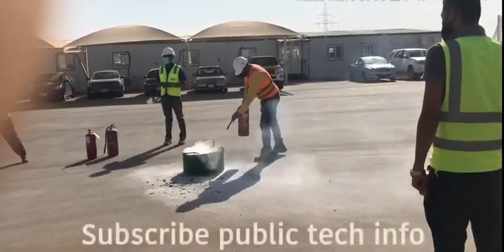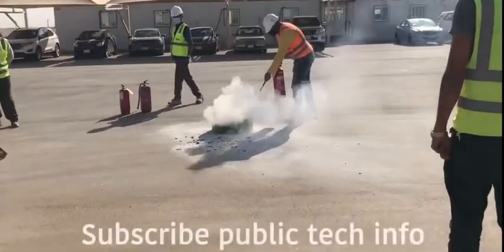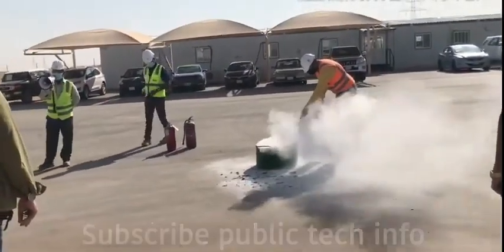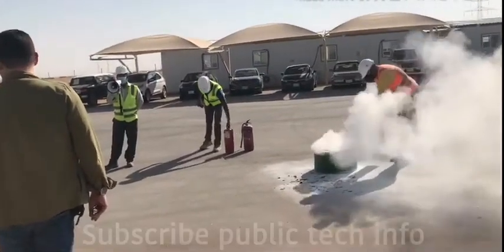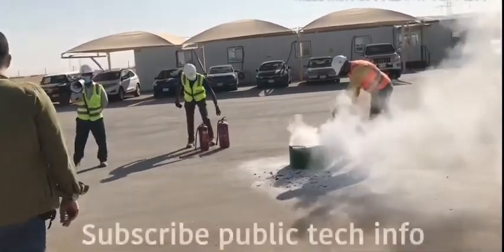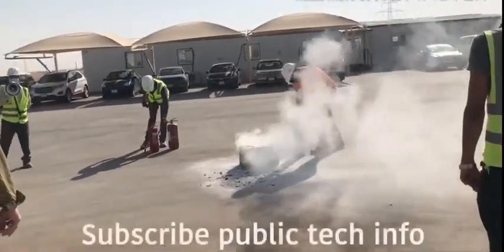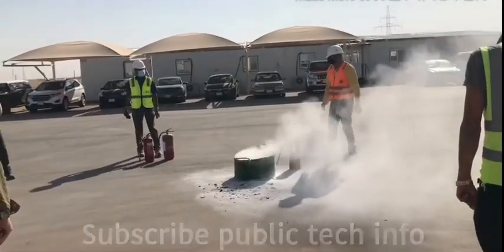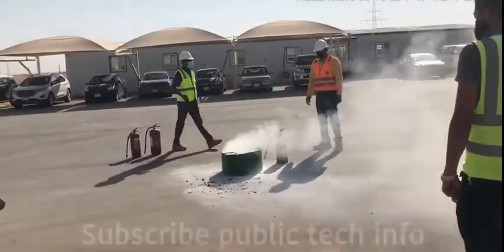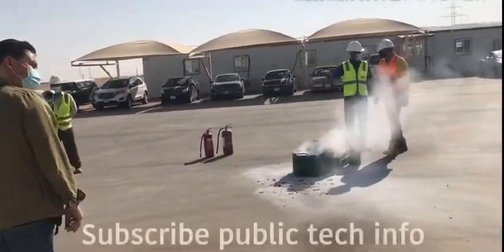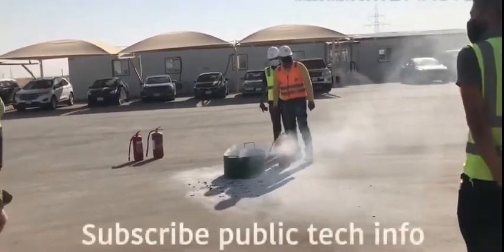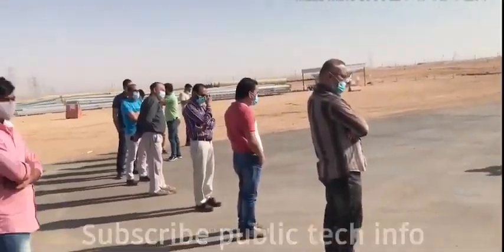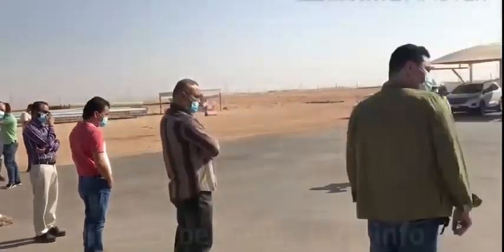The fire extinguisher we are using is dry chemical powder. This is ABC, because this fire extinguisher is the multi-purpose fire extinguisher. So everywhere the one method is the PASS method: pull the pin, aim, squeeze and swing. So everyone should be aware how to operate this fire extinguisher.